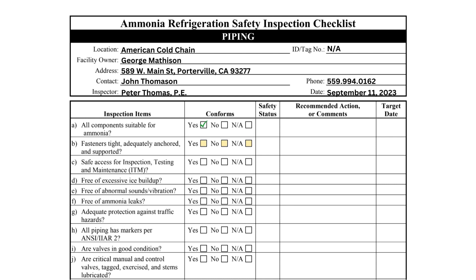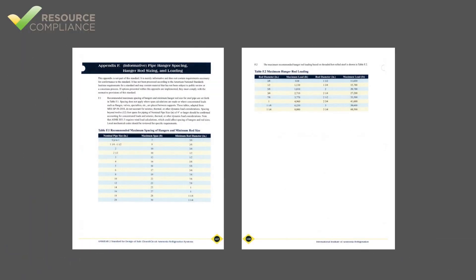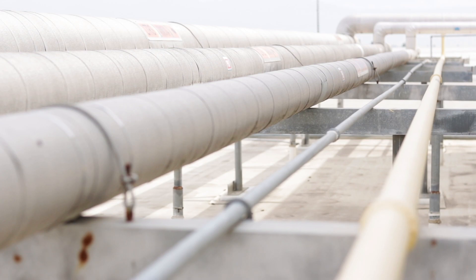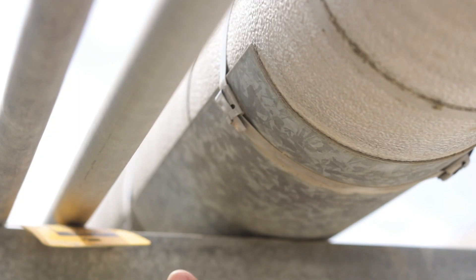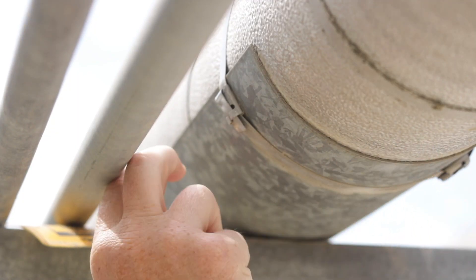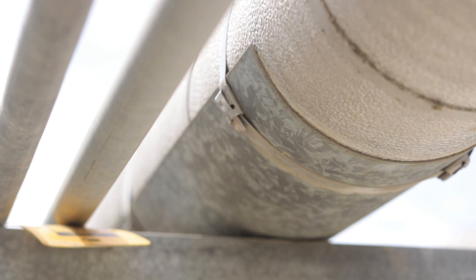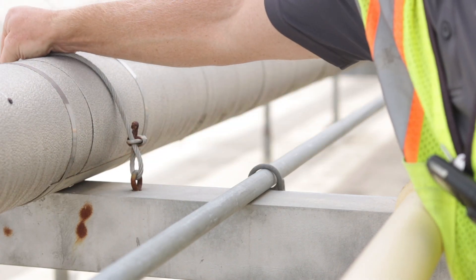Item B requires the inspector to verify that pipe fasteners are tight and adequately supported. Appendix E in the 2021 edition of Standard 2 has a table with recommended spacing of pipe supports based on the pipe diameter. Additionally, the 2019 edition of the IIAR refrigeration piping handbook suggests that pipes be fastened to every two or three supports. U-bolts and strut clamps are commonly used fasteners.